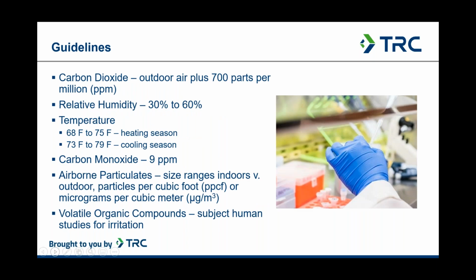Now I'll discuss the guidelines for those indoor air quality parameters. Since CO2 is naturally occurring in our atmosphere and can fluctuate, the guideline for indoors is the outdoor CO2 concentration in parts per million plus 700 parts per million. In urban areas, sometimes the CO2 concentration is a little higher than in a suburban or rural area. So with the 700 plus the outdoor level, you typically end up running around 1,000 to 1,100, maybe even 1,200 occasionally.